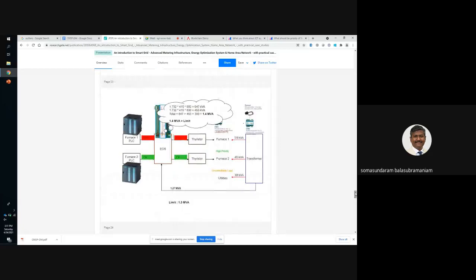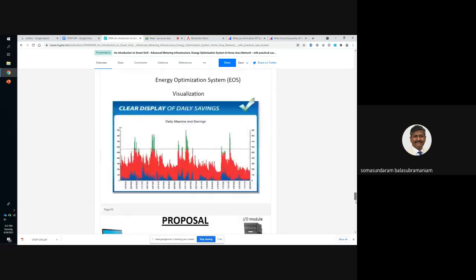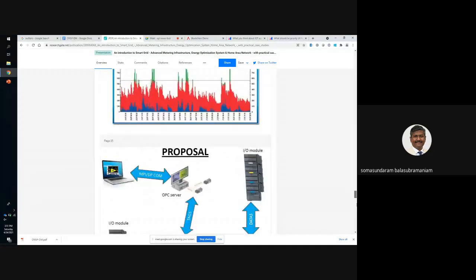When it is an overload, even if the furnace PLC asks for 10 volt, it will not give you 100%. It will only give you 80%, such that the limit is adhered to. The limit here is 1.3 MVA for this particular transformer, which is about 2 MVA. So that is the safe flow, in order to avoid overshoots and other issues.